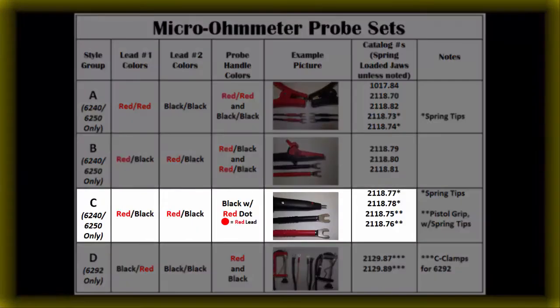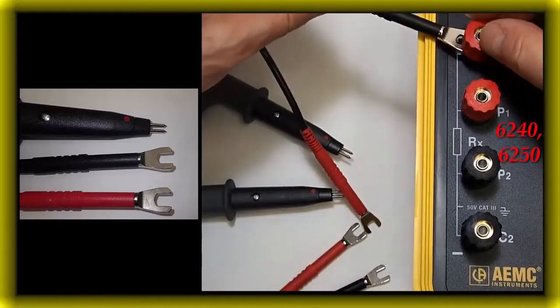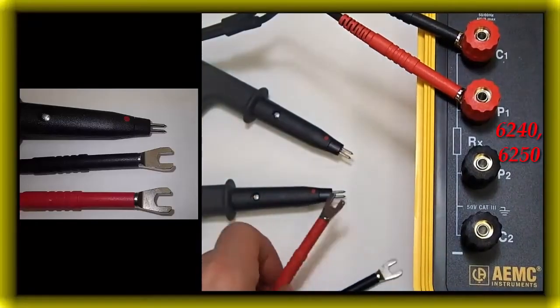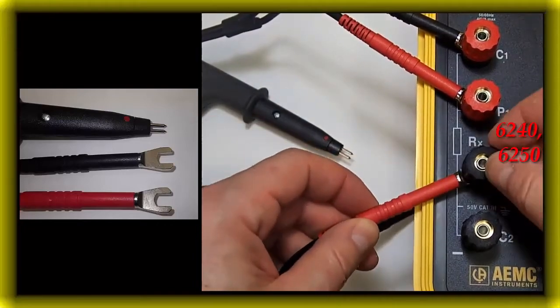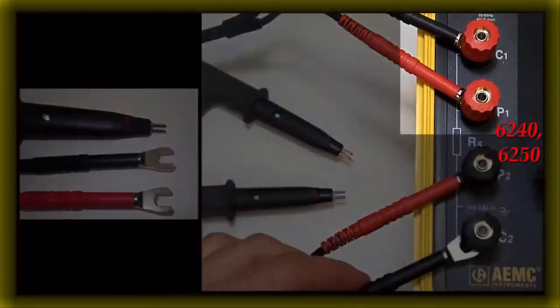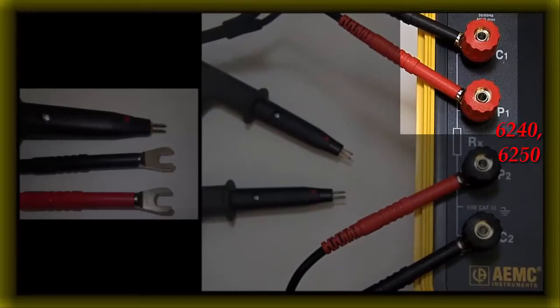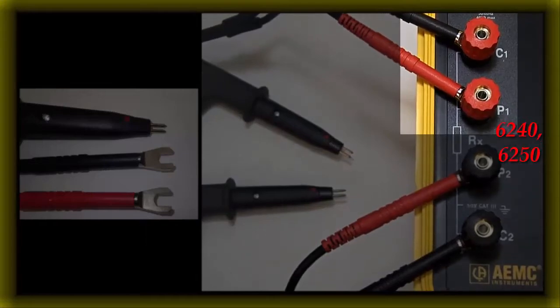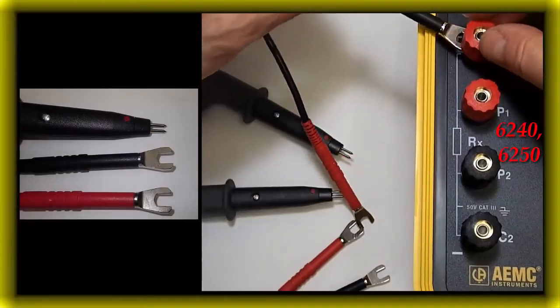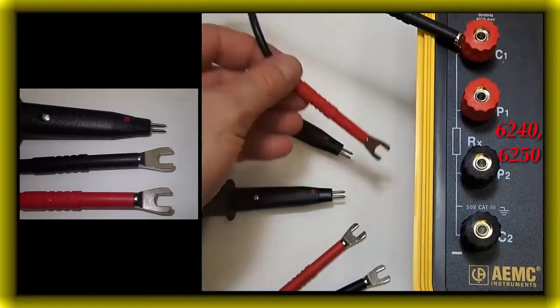Style Group C for 6240 and 6250. When using the 4 part numbers from Style Group C, where the leads are red, black, and there's a red dot on the probe tip, then the connections will not match the color coding on the instrument's terminals. In these cases, the black lead will always connect to a C terminal, and a red lead will always connect to a P terminal, or vice versa. Note, these leads are not approved for use with the model 6292.